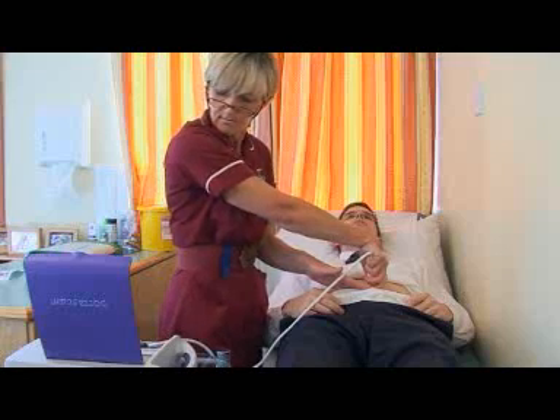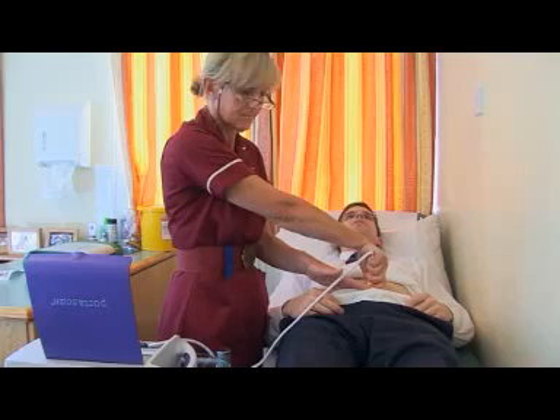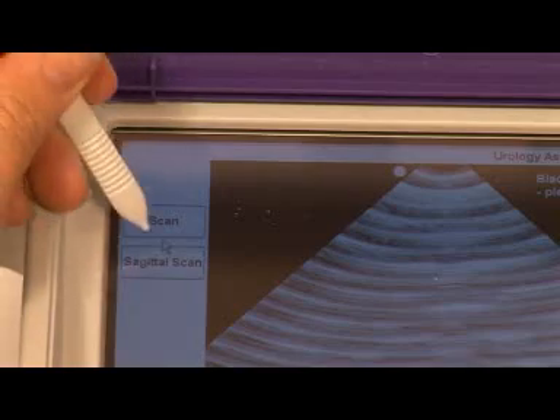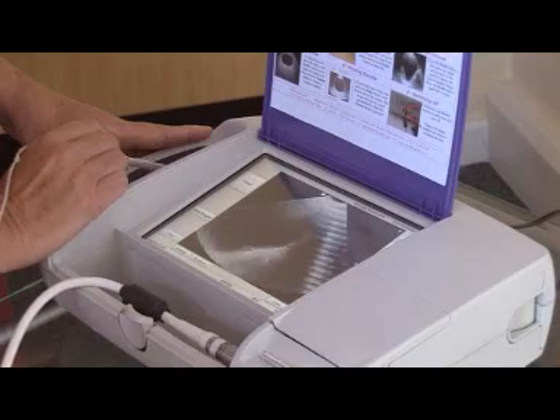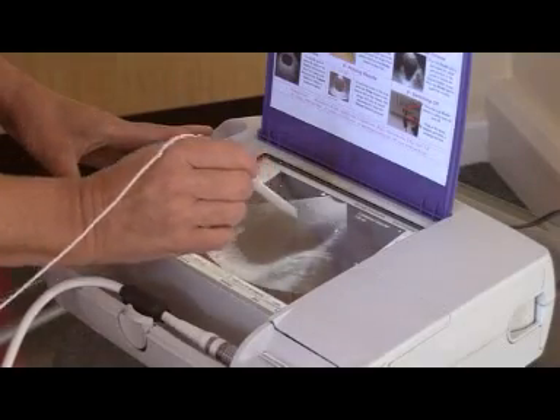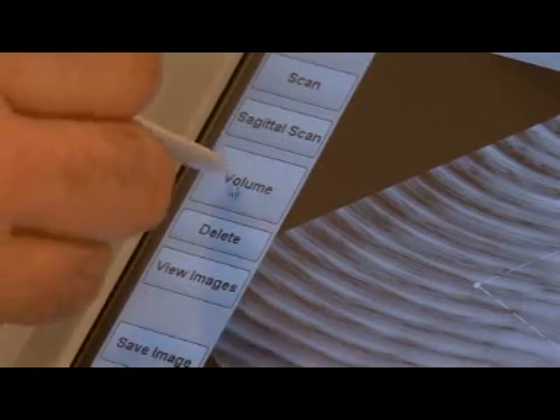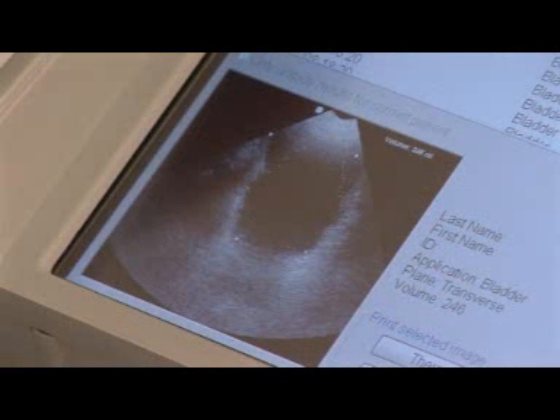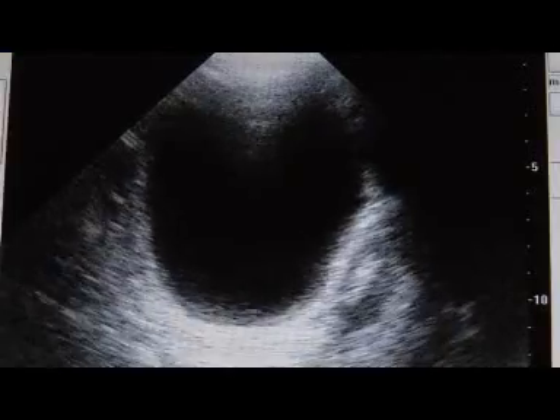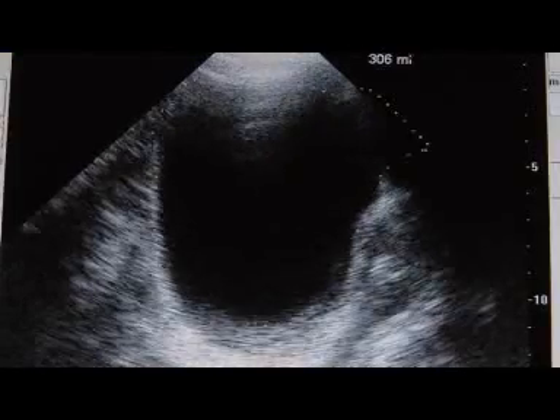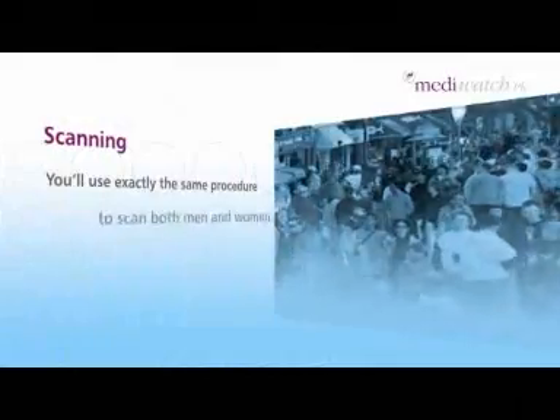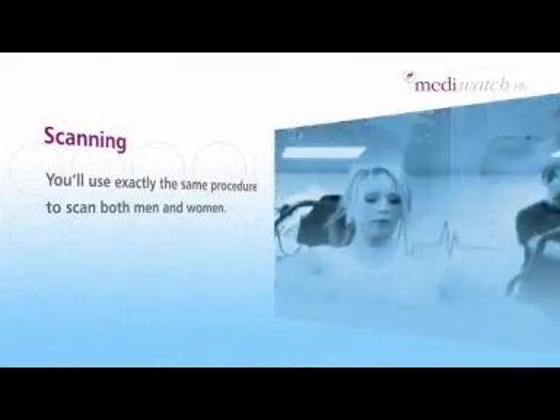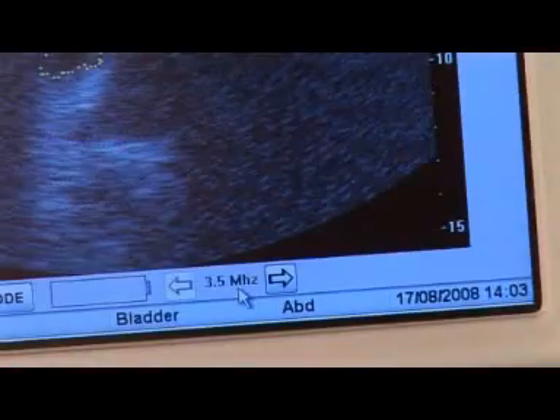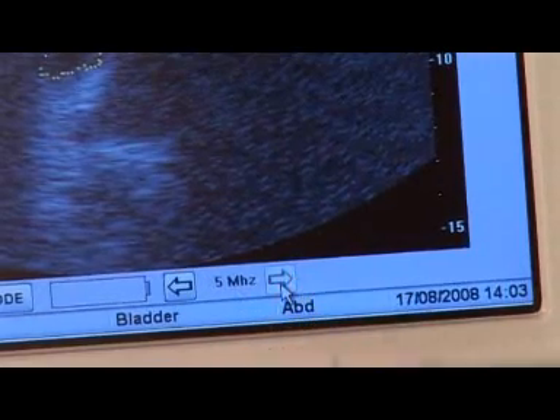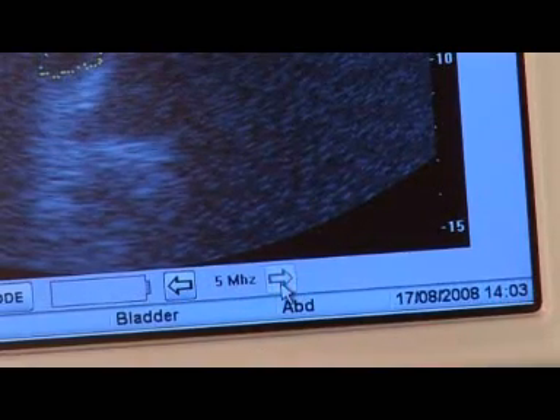As with the transverse scan, if you feel that you can obtain a better picture, press the sagittal scan button again to repeat this part of the scan only, or mark points manually and press volume to recalculate. A transverse scan of most bladders is roughly square, especially in women, but the sagittal scan is more of a triangular shape. You'll use exactly the same procedure to scan both men and women. For pediatric scanning, increase the probe frequency from 3.5 MHz to 5 MHz.